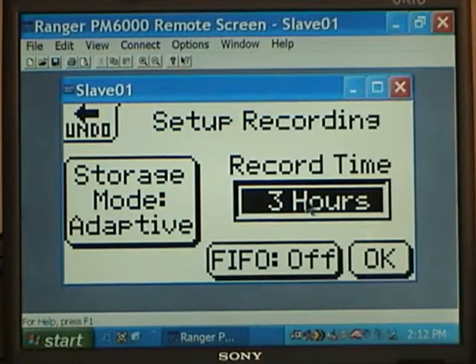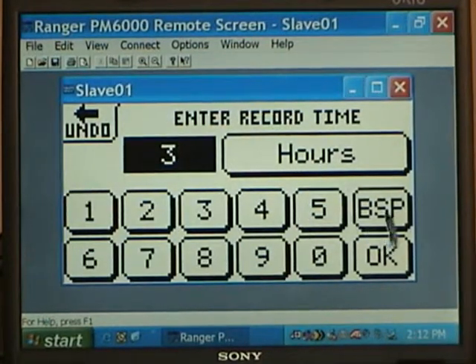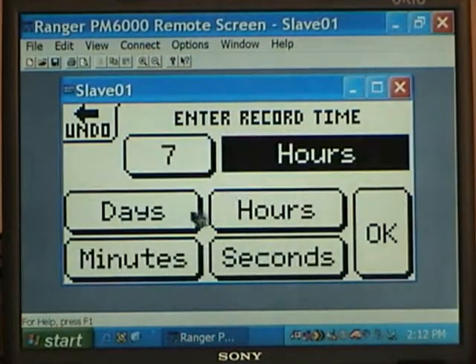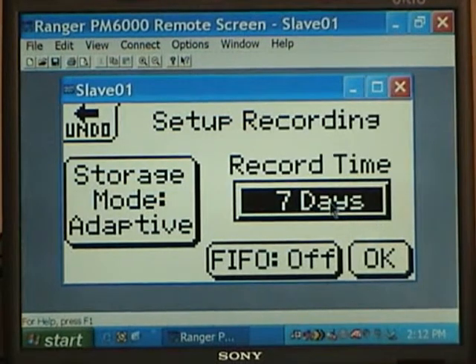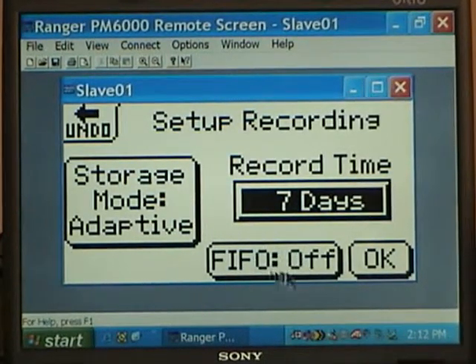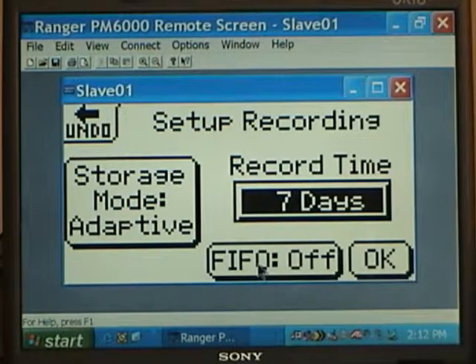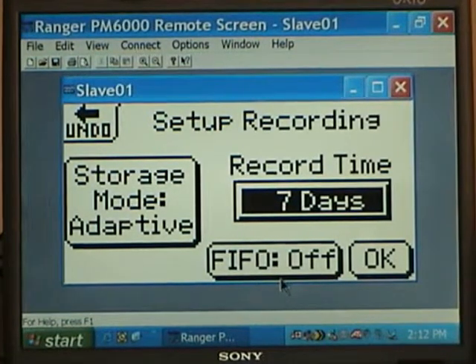You can see how easy that is to do. Just to go over it again, if I wanted to backspace and change it back to the original of 7, I click on days and say OK, and it's back to 7 days. We also have first in, first out turned off right now. However, you could turn that on, and what that does is it's a rolling memory. After the memory gets full, it starts overwriting the older data with newer data.